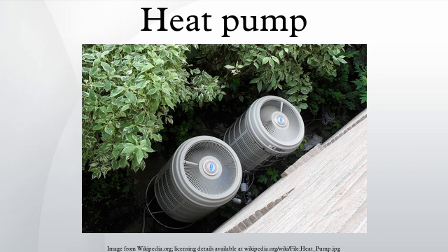The working fluid, in its gaseous state, is pressurized and circulated through the system by a compressor. On the discharge side of the compressor, the now hot and highly pressurized vapor is cooled in a heat exchanger, called a condenser, until it condenses into a high-pressure, moderate-temperature liquid. The condensed refrigerant then passes through a pressure-lowering device, also called a metering device. This may be an expansion valve, capillary tube, or possibly a work-extracting device such as a turbine. The low-pressure liquid refrigerant then enters another heat exchanger, the evaporator, in which the fluid absorbs heat and boils.